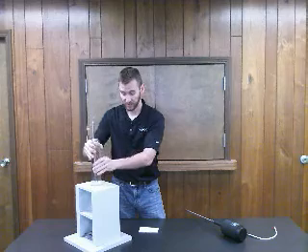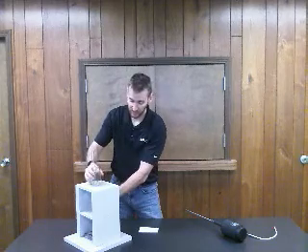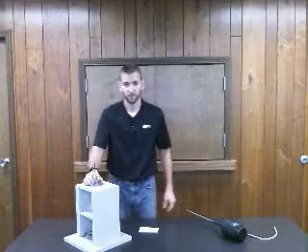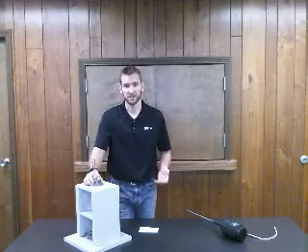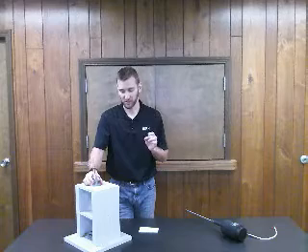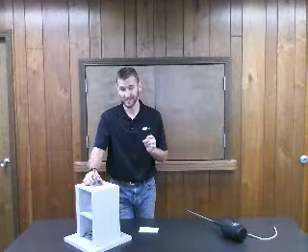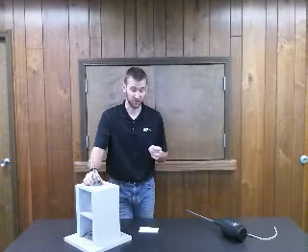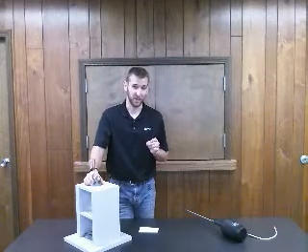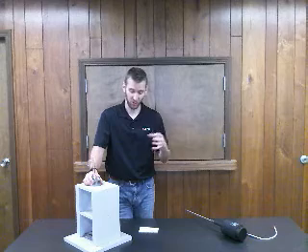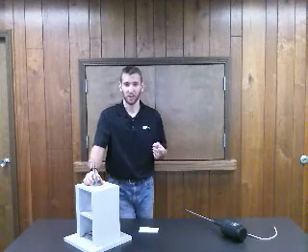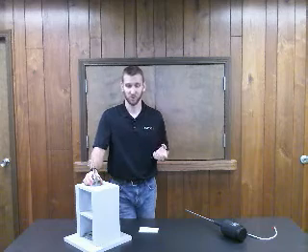This would indicate that we now have a gap between the wall of the well and the ice mantle. Now this is important because if the ice mantle was still completely against the well, then we would be measuring the ice temperature instead of the triple point temperature. With a small gap and water allowed to go into that space between, we're able to measure the true triple point water temperature.